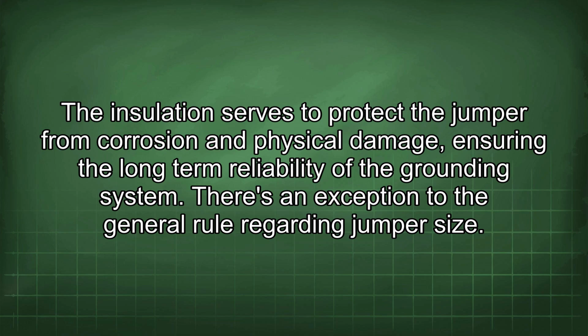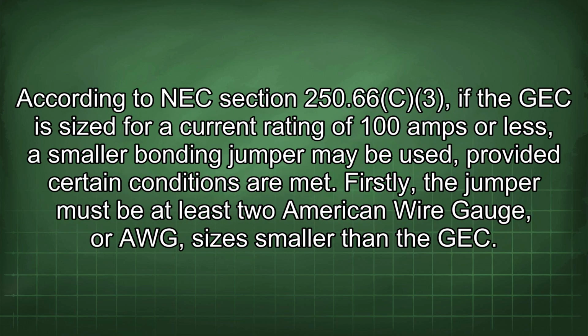There is an exception to the general rule regarding jumper size. According to NEC section 250.66(c)(3), if the GEC is sized for a current rating of 100 amps or less, a smaller bonding jumper may be used, provided certain conditions are met. Firstly, the jumper must be at least 2 American wire gauge, or AWG, sizes smaller than the GEC.